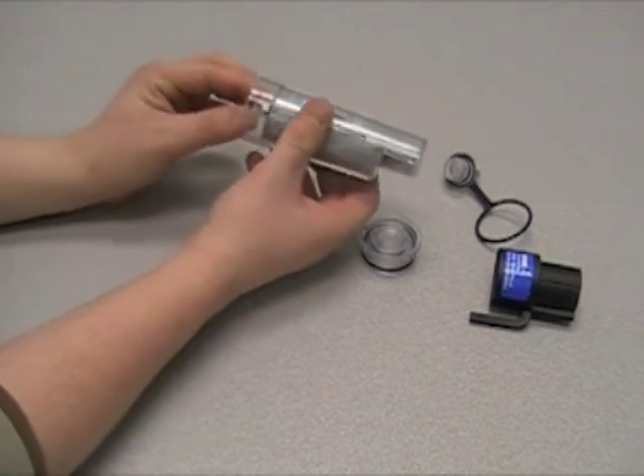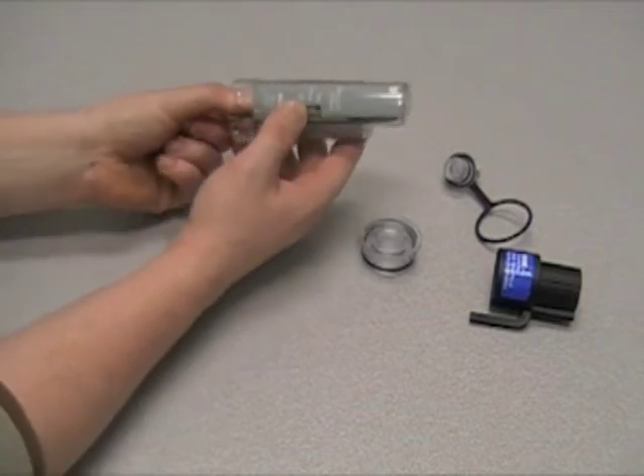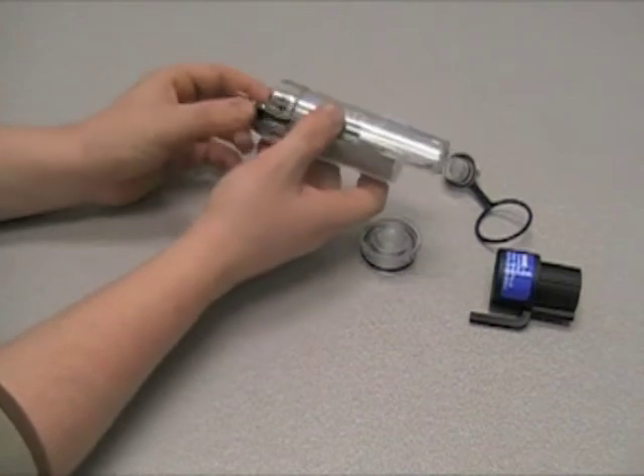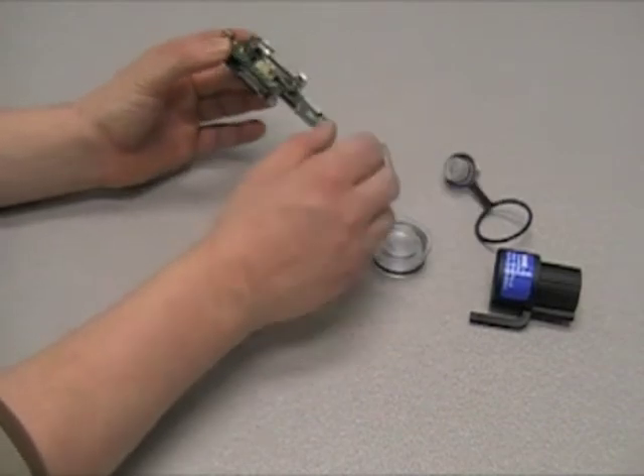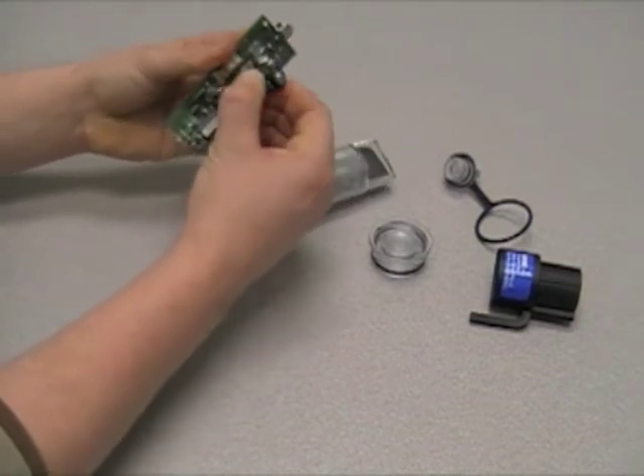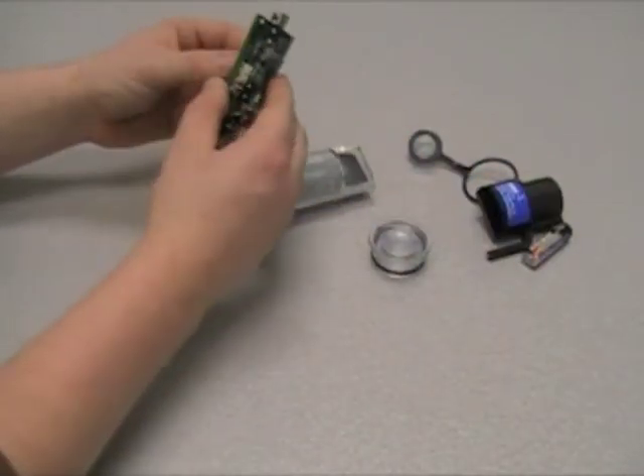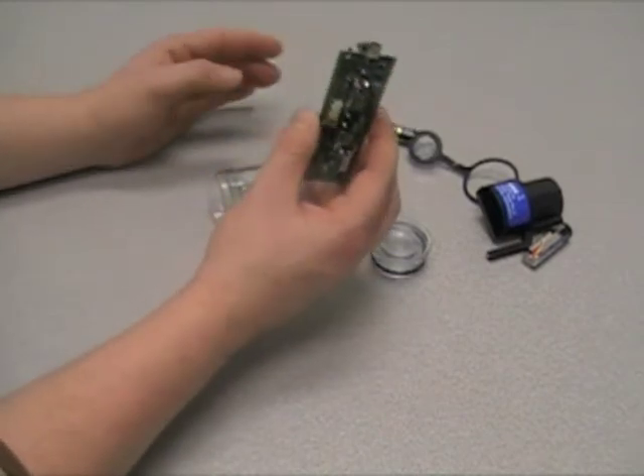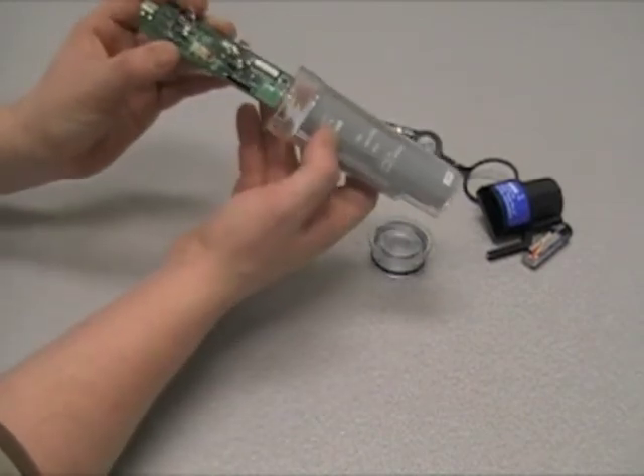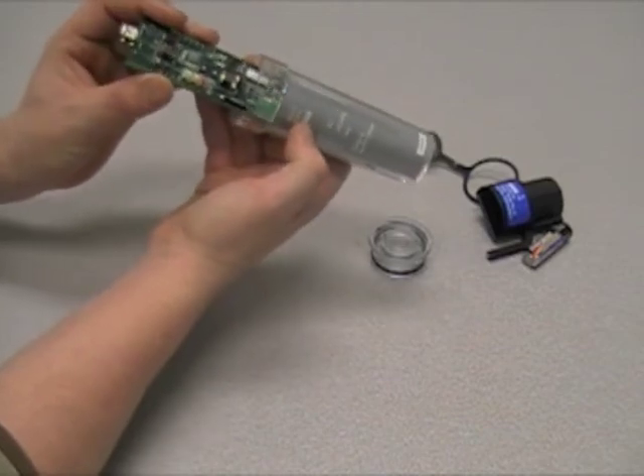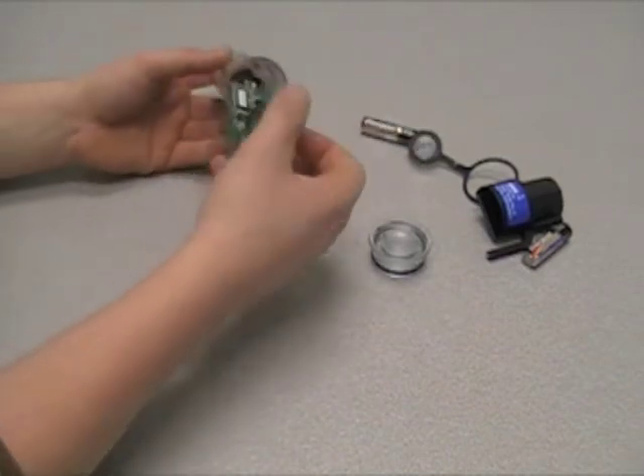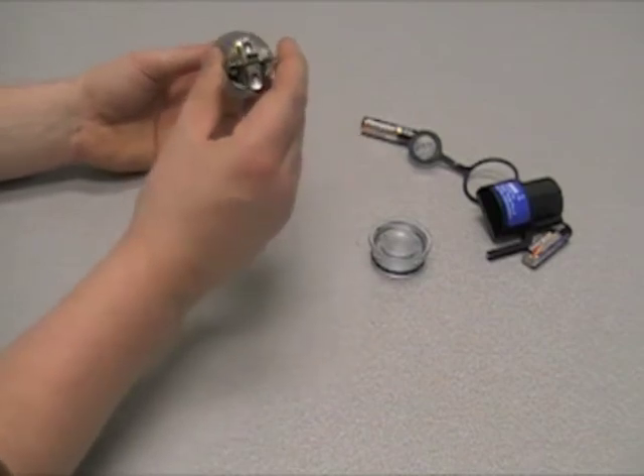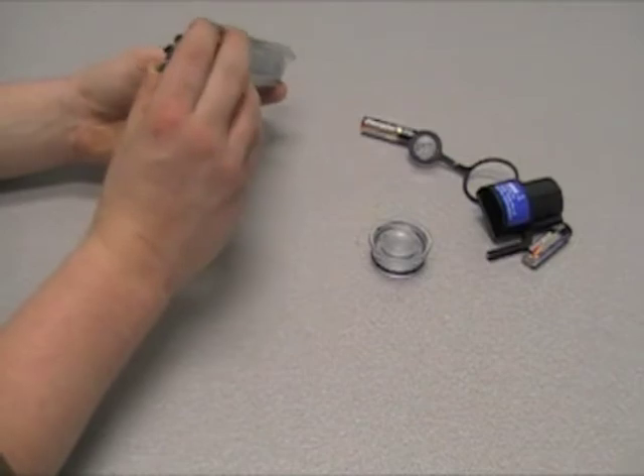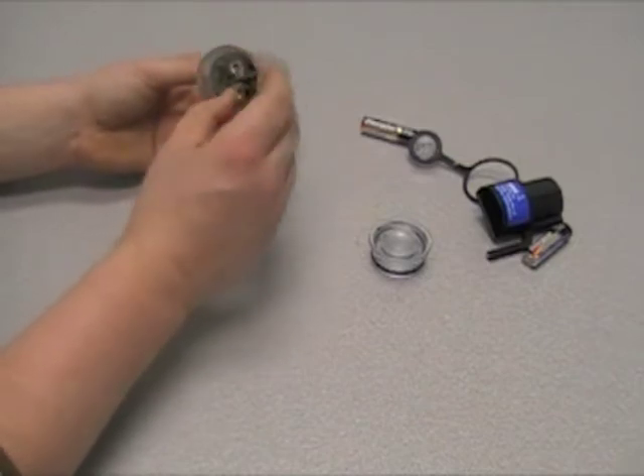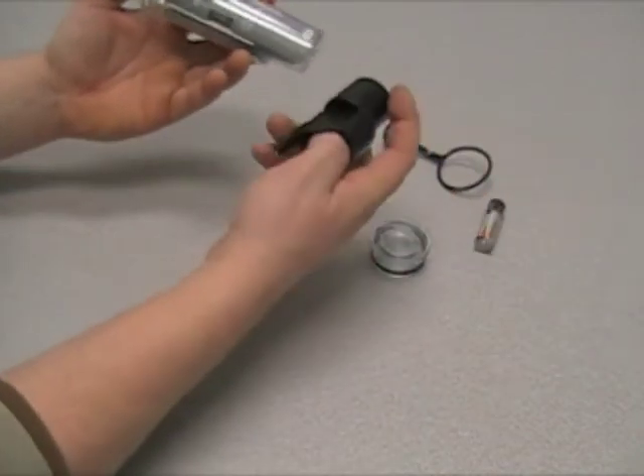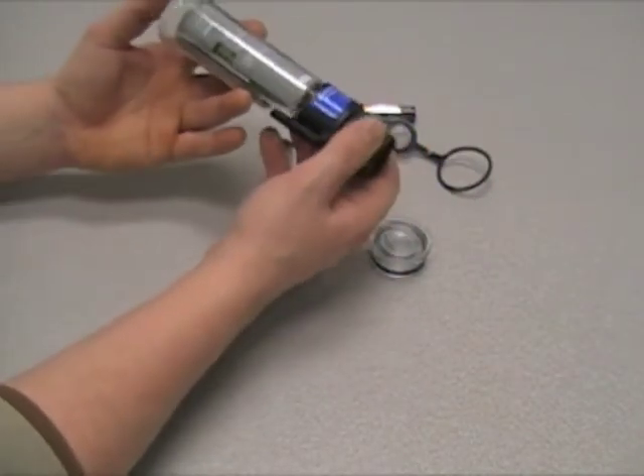The next thing we need to do is remove the batteries from the circuit board inside, so we just have to pull this out. Remove both batteries. Then we need to put this board back inside the case. We need to have the case on there for this to work properly. Be sure when putting this in here, put them right back within those grooves. And then we're going to need the coupler back on here because we need to activate the reed switch internally here.